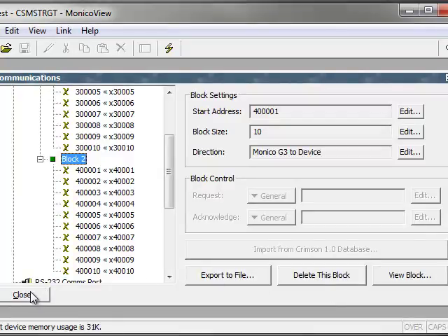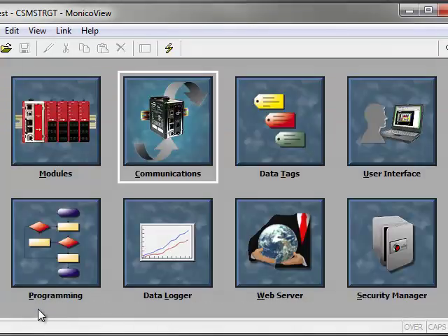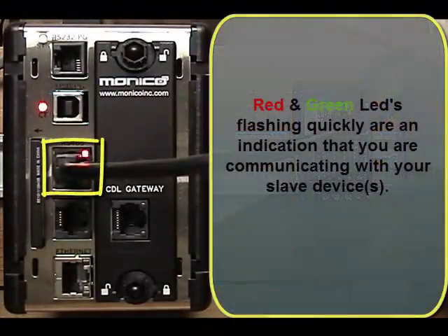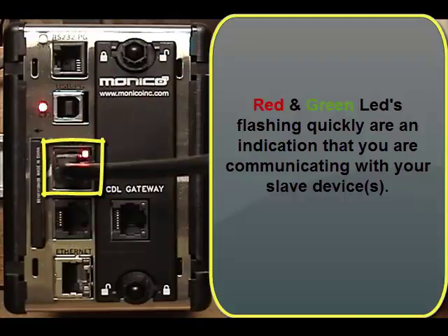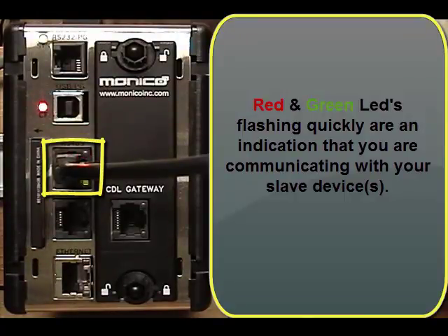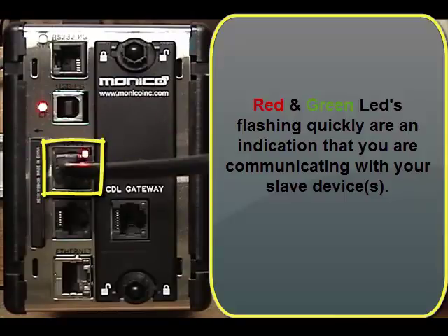If you're not connected to the gateway and you don't have MonicoView open, you can look at the LEDs on the top of the gateway and determine whether or not you have communications with the device. In this example, you'll see the red and green LEDs alternate, and they're going very fast — they're getting data. The green is us sending out a request; the red is us getting the data back. This is a good indication that you've got communications with your device or devices and that you are getting data.